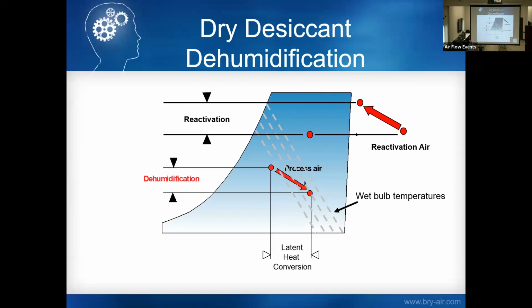So here again, this is what I talked a little bit about. The process air stream: we're going to take the moist air. It actually gets heated up, but it goes down on the psych chart as it gets drier. As you see, the reactivation air, typically reactivation is outside air. That air then cools down and picks up moisture during the cycle.